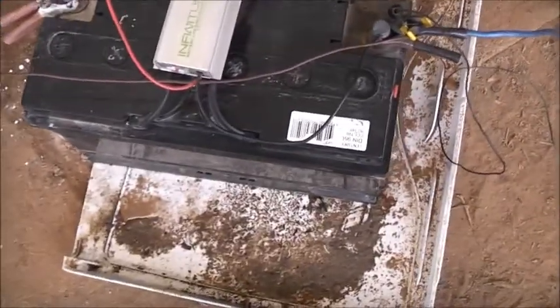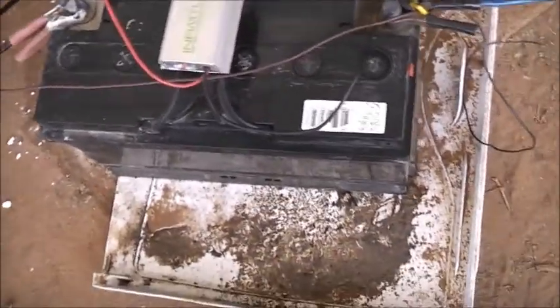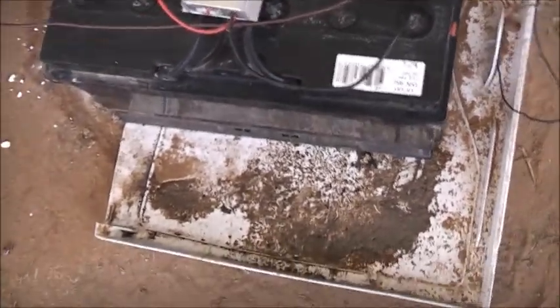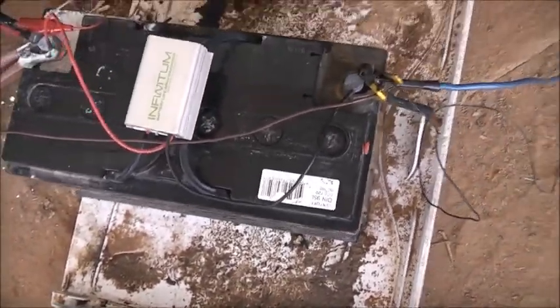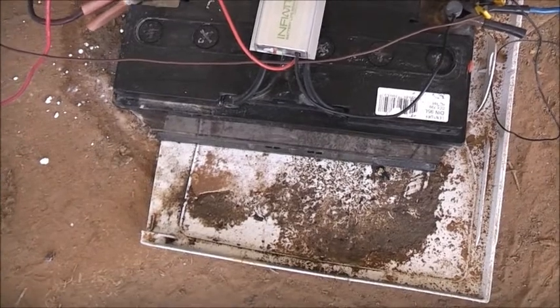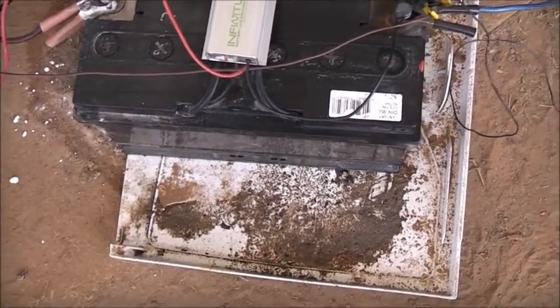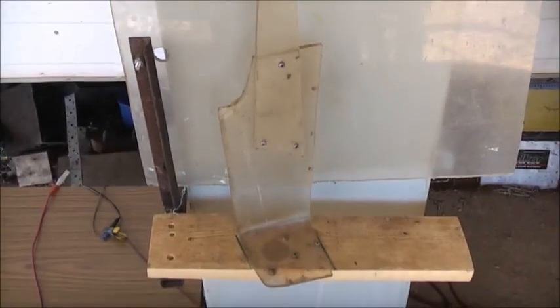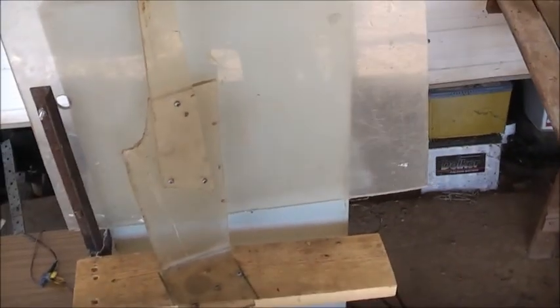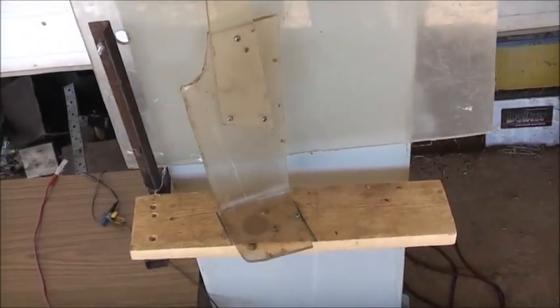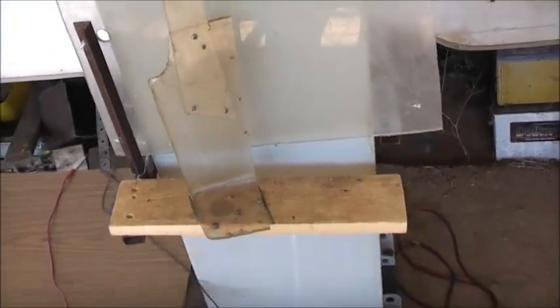Just in case something worse happens, those gloves will be a bloody lifesaver. So I'm trying to see if any class 4 ones turn up, and I'll see if I can get some for a reasonable price. Class 2 probably will do 20 kV, but they're only tested to 25 or 30 kV - it's best to be safest and get the 40 kV rated ones.